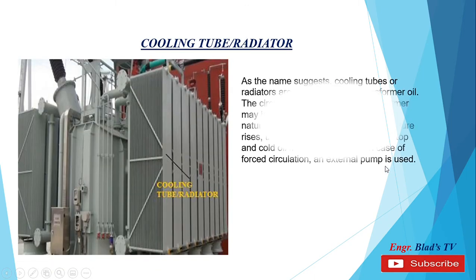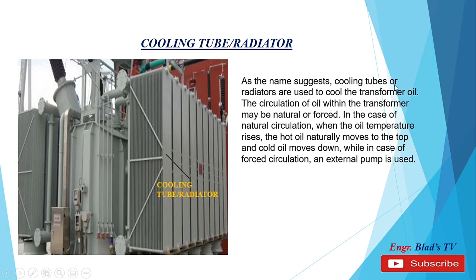Cooling tube or radiator. Cooling tubes or radiators are used to cool the transformer oil. The circulation of oil within the transformer may be natural or forced. In the case of natural circulation, when the oil temperature rises, the hot oil naturally moves to the top and cold oil moves down. While in the case of forced circulation, an external pump is used. In this picture we can see the cooling tube or radiator, sometimes called cooling fins.